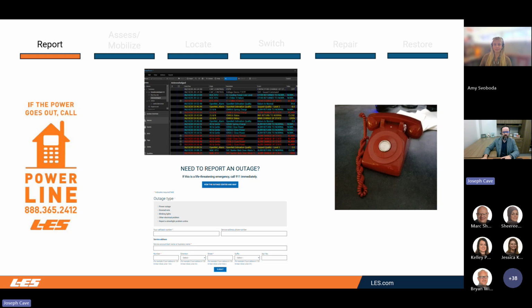When we get customer outages, we don't know until we have some kind of indication that we have an outage. One of the first ways we get that information is through our SCADA system. This is a screenshot of what our SCADA system looks like — essentially computers out on our system monitoring our equipment, bringing back information like alarms. When a breaker opens, we get that notification through SCADA, it shows up on a display for our operators, and they respond accordingly.